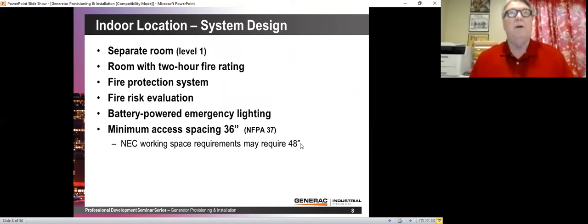All right, separate room. Level 1, remember level 1 is emergency generators for life safety. Those need to be in a separate room if, of course, they're indoors. That room should have a 2-hour fire rating. Typically, we'll have a fire protection system, which is almost always water sprinklers. The fire risk evaluation, battery-powered emergency lighting, and minimum access spacing of 36 inches.